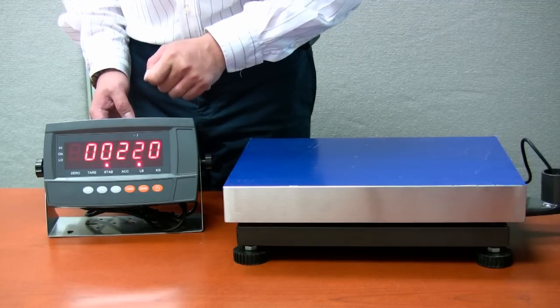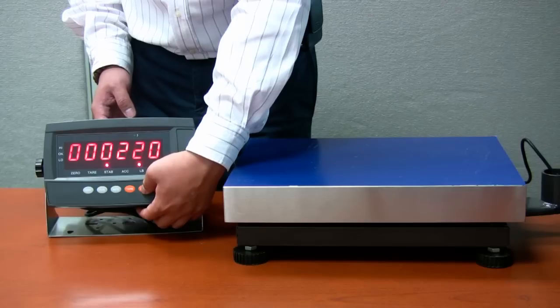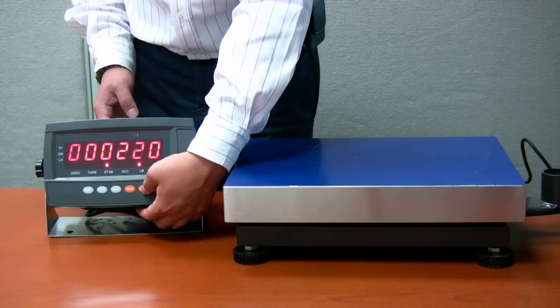Press function key to move the blinking digit and the zero key to change the value of the blinking digit to enter the weight of your calibration weight.